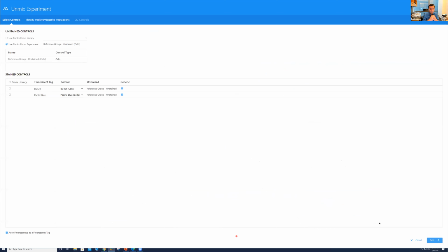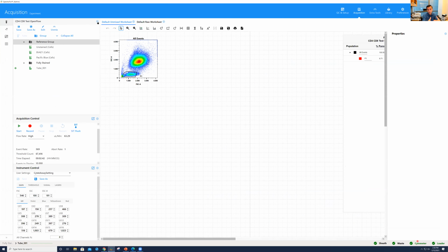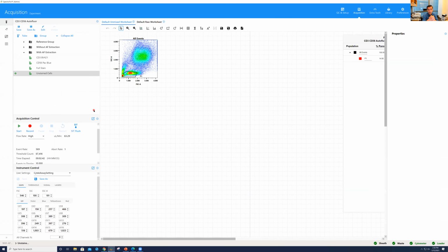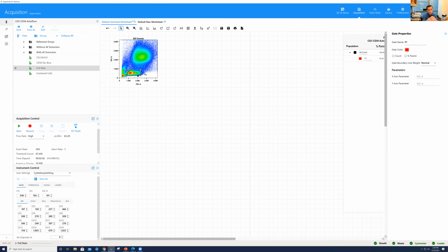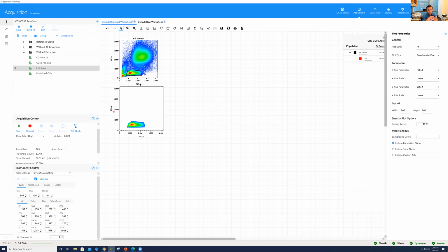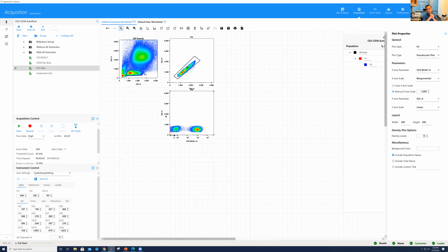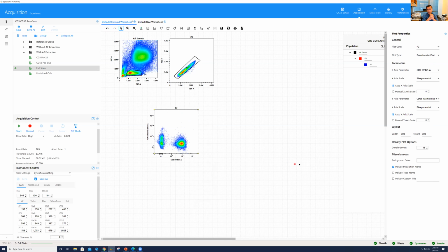Yeah, and I should say that if you think of it, always using the autofluorescence as a fluorochrome should be the way to go, right? It makes sense because you're providing more information, and hopefully the correct information, to be able to unmix correctly. There are two issues. One of them is that maybe you don't have the possibility, because you have a heterogeneous sample, to gate the exact autofluorescence of the cells that you're trying to unmix. But also, there have been cases where using the autofluorescence extraction doesn't give you the best result. And this has been reported by Cytek.